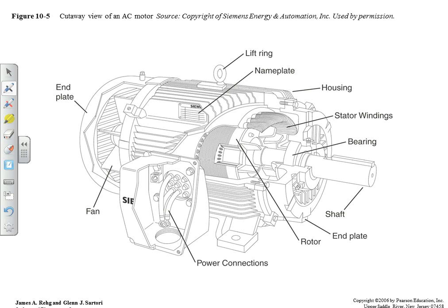Okay, so we took it apart. It had a hole going through those windings the size of a $50 bill. We never smelled it. It didn't open a breaker. There was no overcurrent. We didn't see any fireballs going. And the space is manned 24/7. So those things can happen.